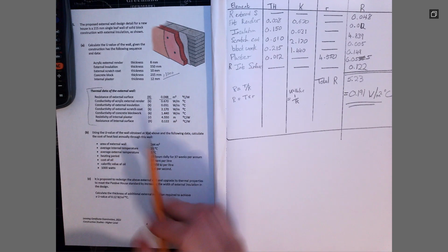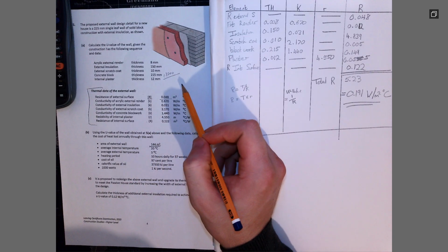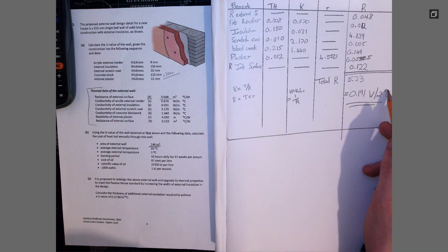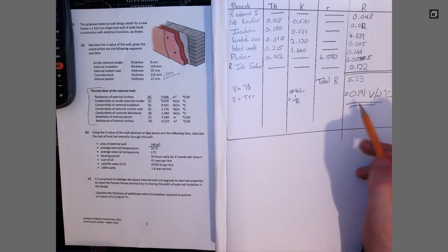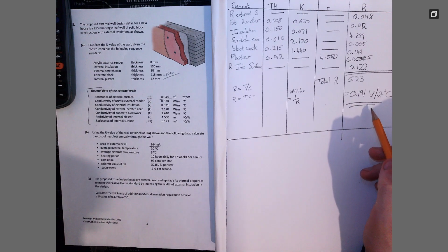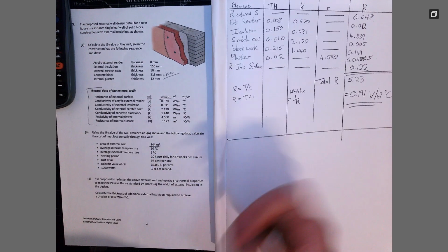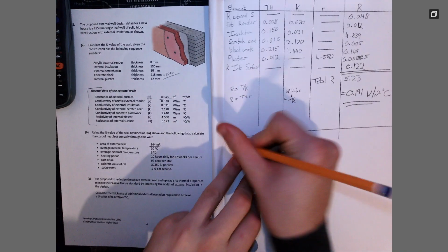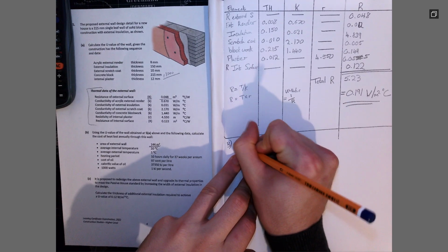In this case we have a wall. So the area of the wall is 144 meters squared, right? The U value itself only gives us a general term, watts per meter squared degrees Celsius. What that means is that it's only telling us the rate at which heat goes out through a wall in a given second. You see it's meter squared there, meter squared down here. So what we first have to do is calculate the heat loss, and obviously label everything as well.